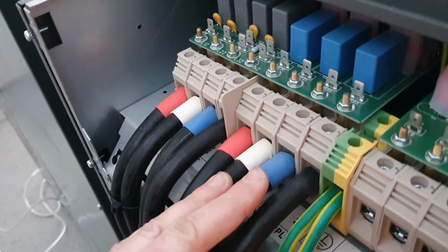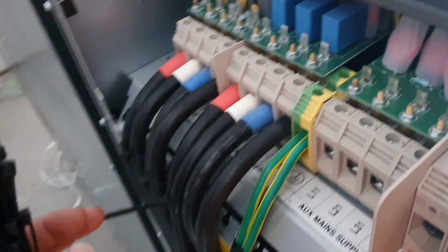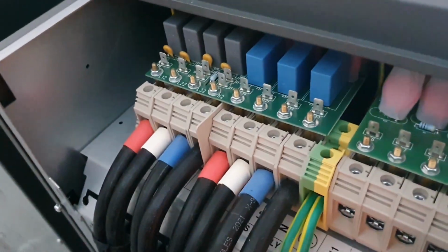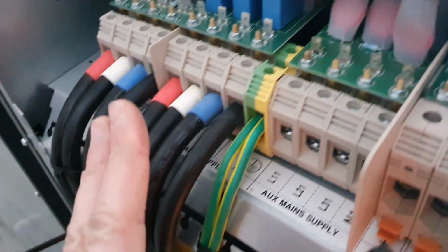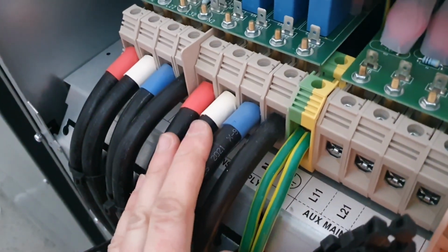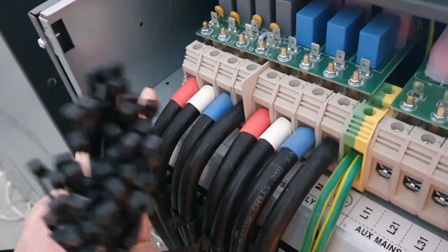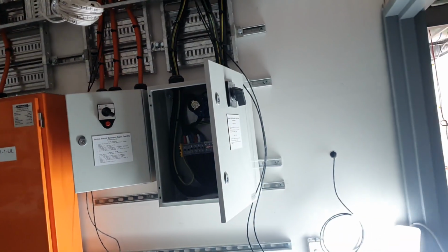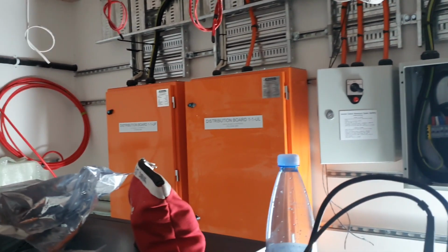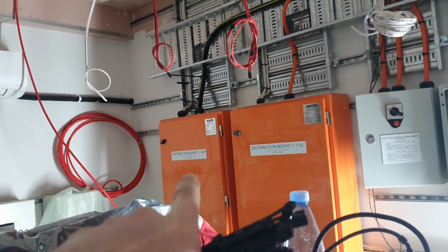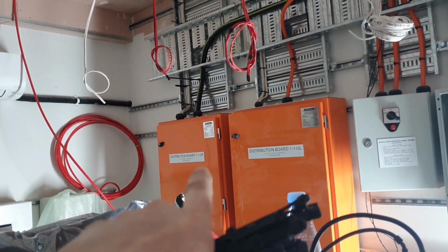Had to remove these to megger all this electronic nonsense in there. So in a nutshell, this is the super quick version of how this works: feed from the main switchboard, this set here goes to the bypass switch over there, and from the bypass switch it goes into the board on the left, the UPS power board.